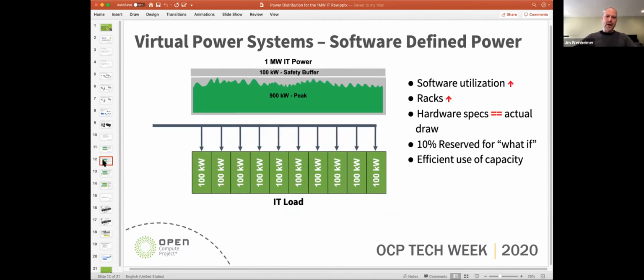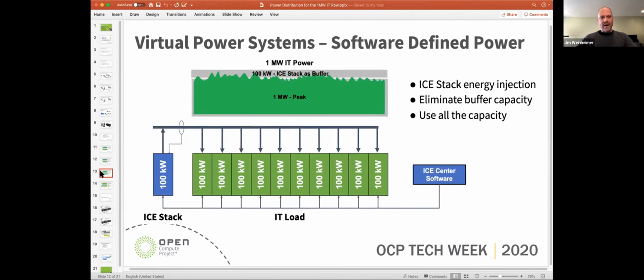So even though you're now using the hardware more efficiently and your actual draw is equal to the hardware specs, there's still a small buffer just in case. On the next slide, you'll see we're now monitoring the system's power draw, and we've added an energy storage system in the form of batteries that can supply some of the power to the IT load when it's needed. The energy storage systems here replace the buffers that are usually reserved on the physical infrastructure that allows all the capacity of the purchased electrical system to be used.